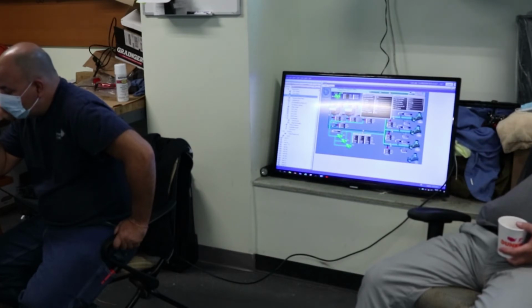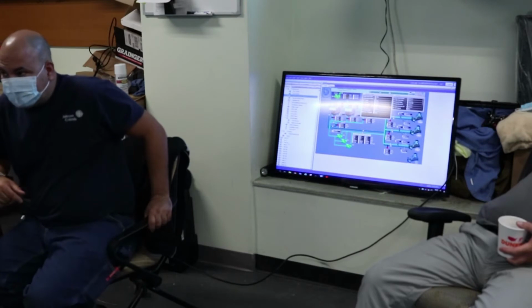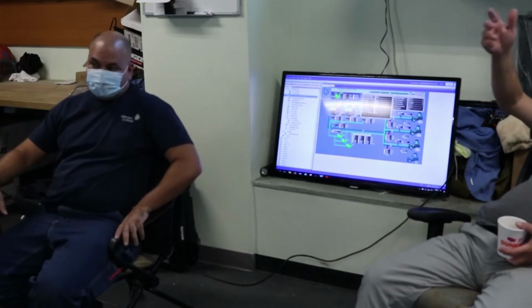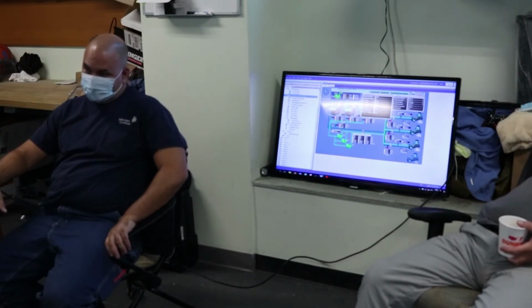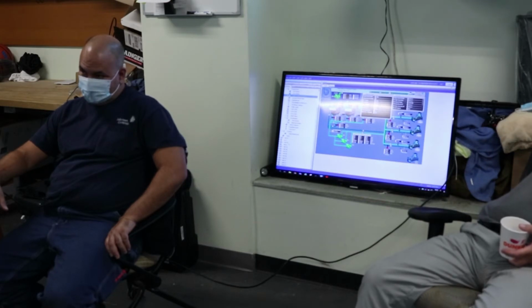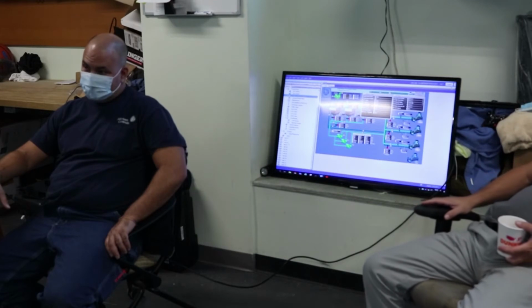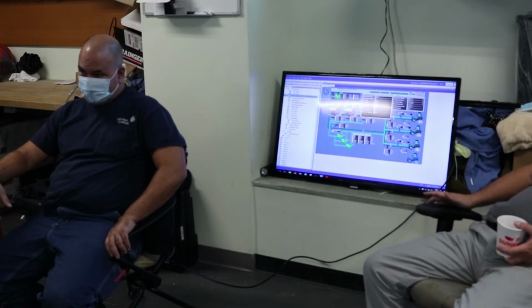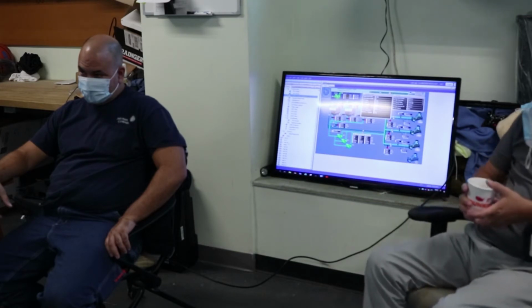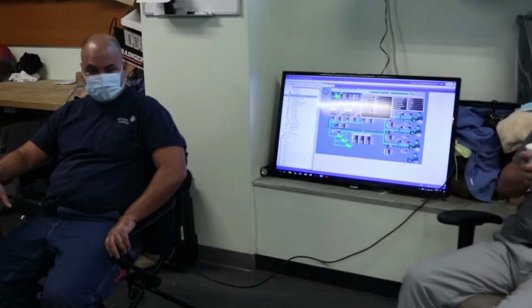I'm gonna go to Mickey and Scott to see what the future is for this building. Maybe they want to go straight, because you've got a 350 gallon tank. Is that building still going to be used for inpatient? Do they need showers? Building 10, there's no more showers. There haven't been showers for years, yet we have a 350 gallon tank over there. Building 11, we've got a 50 gallon electric water heater that does the whole building, no problem. Throw an electric water heater in there. It's not like you don't have enough electric around this place.